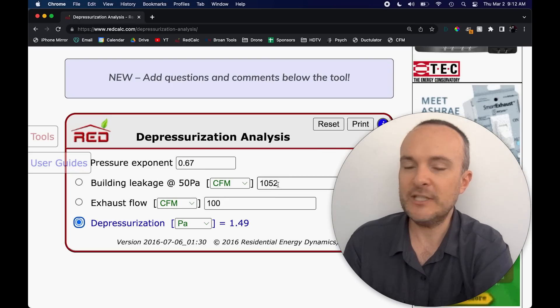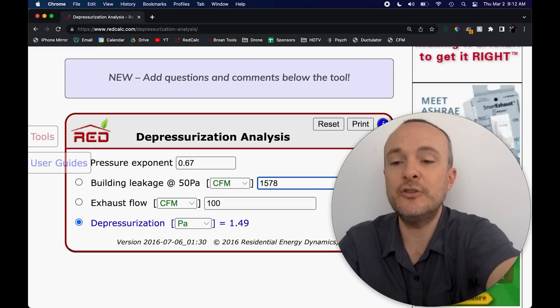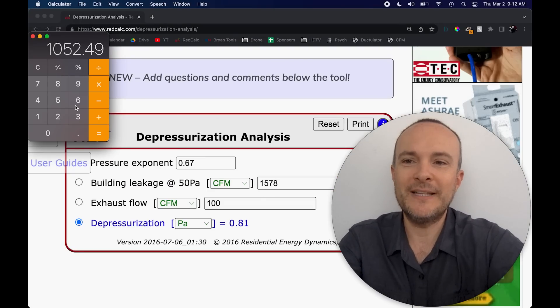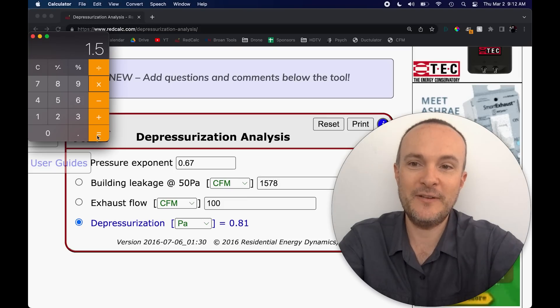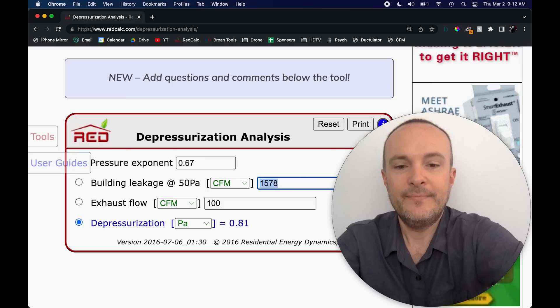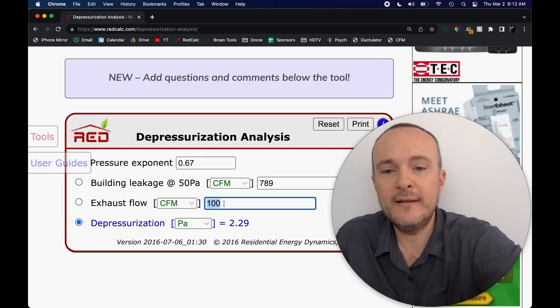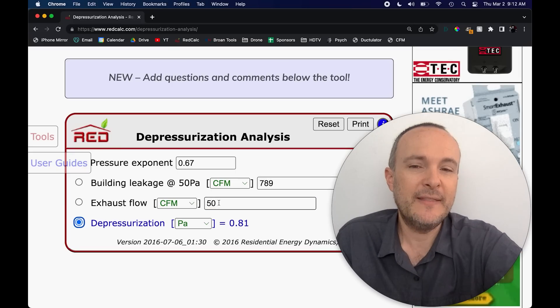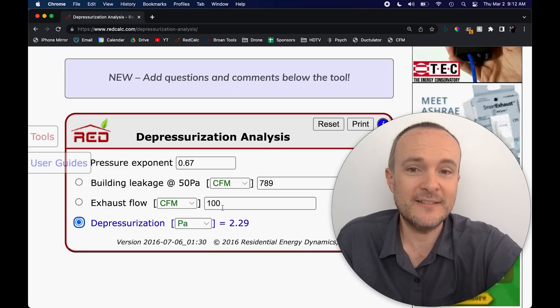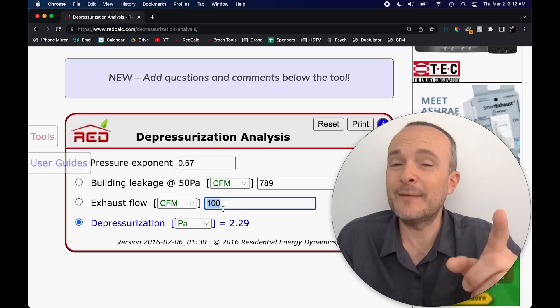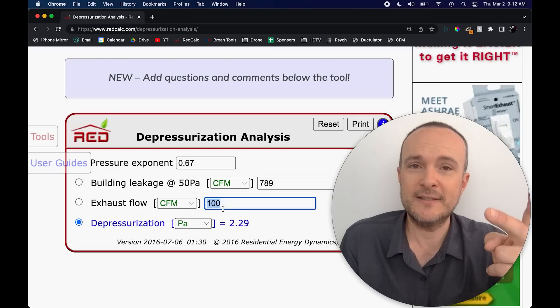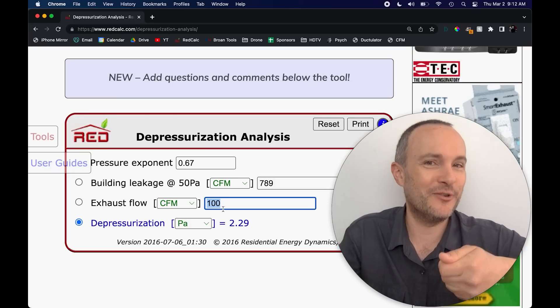So let's now take us to one and a half ACH 50. We're going to go back to our 1578 and then divide that by two. Or we can just simply divide this back down by two to get to our one and multiply this by 1.5 ACH 50. And that gives us 789. Now, if I run even just one exhaust fan in this house, I'm nearing one Pascal. That's starting to worry me. If I run two, as you saw, we are at two and a half Pascals. That's well over the range of backdrafting. Something like an atmospheric draft water heater can be backdrafted with two Pascals of depressurization in the whole home.